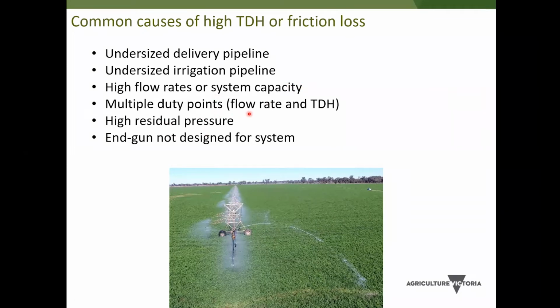Having multiple duty points. So having a pump system that's connected to different irrigation systems, each requiring a different flow rate and a different total dynamic head or total pressure, results in higher residual head in some of those irrigation systems. And so on some parts of the system, we can have much higher energy costs than we should have. And that's where variable speed drives come in to reduce that residual head. And we'll talk about that with Sam's system as well.